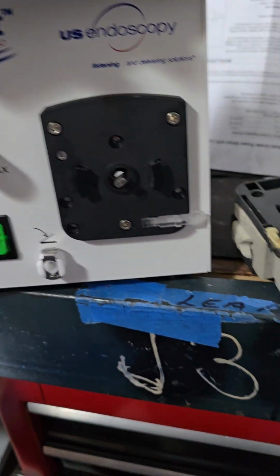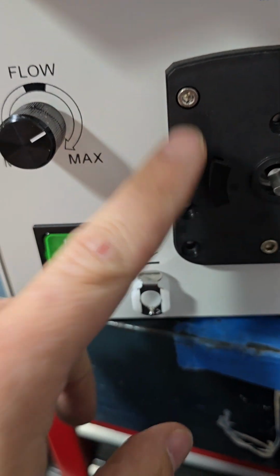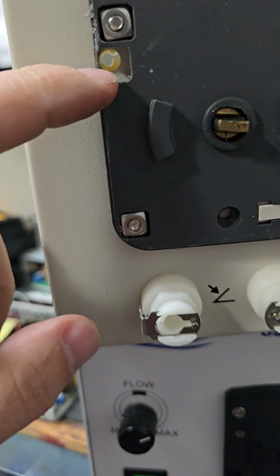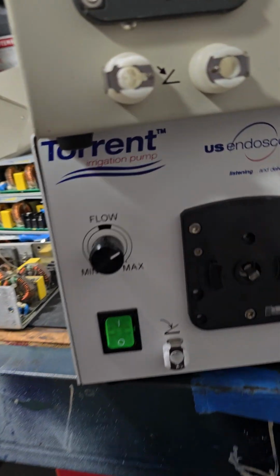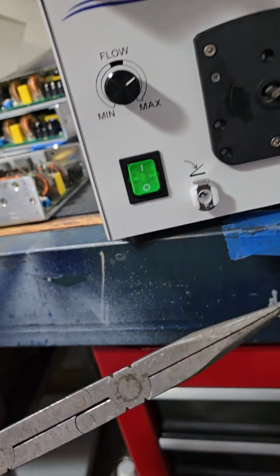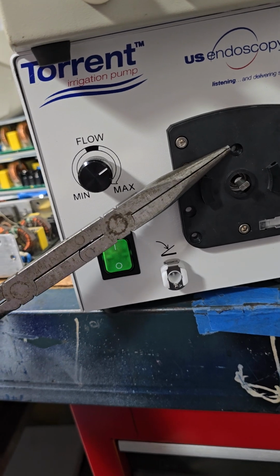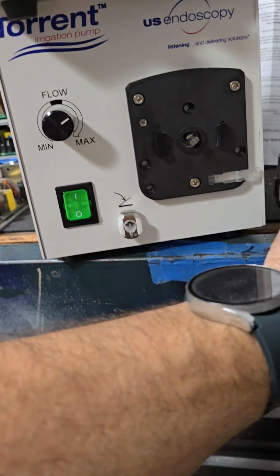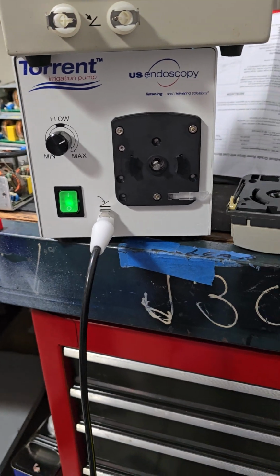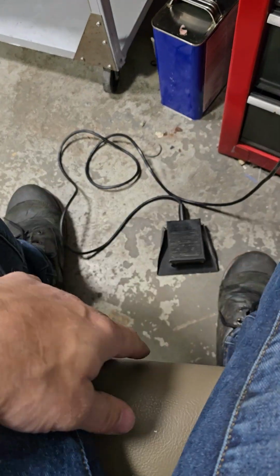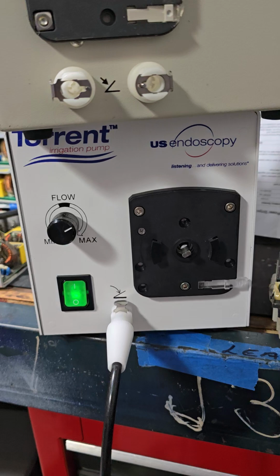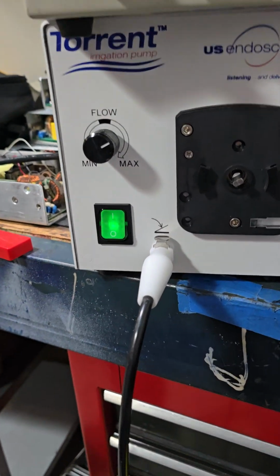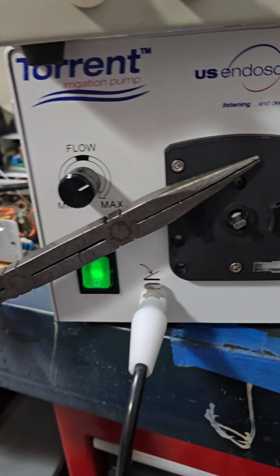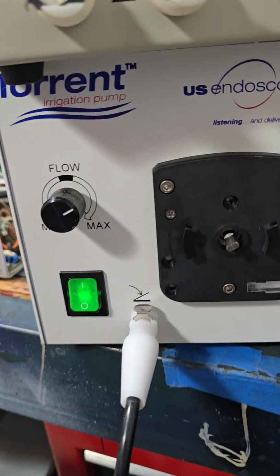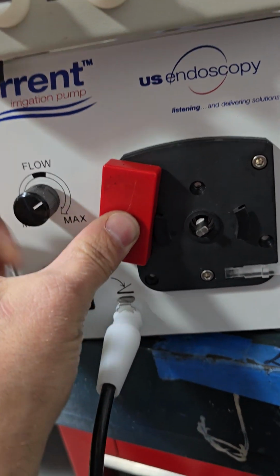Anyway, so this one, see the screw right here? Tell me that's where the sensor is. Here it's all cut out. So the easy thing you can do, one of 2 things. Either A, get some piece of ferrous metal, put it right here, and then hit the foot pump. And if something still doesn't happen, get a magnet. So for this one, there you go, foot switch. It's just an air switch, but you can hear it clicking. Okay. Check, ferrous metal check. Nothing works. Okay. Means the magnet is in the pump head.